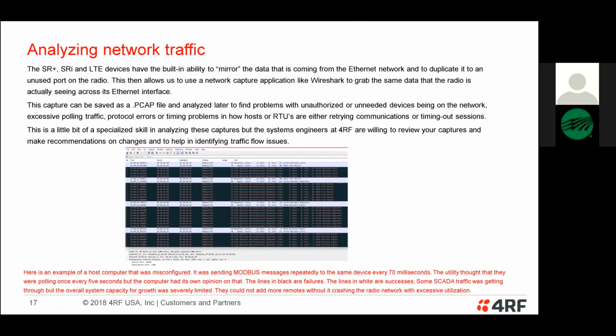And yeah, I agree with them. It shouldn't be a problem. But until we did a packet capture and looked at what was really happening, we weren't able to find out that there were so many reattempts by the host to get data that it was basically killing the entire network. And they were using a Modbus system because this is actually a water utility. While it was working with only a few remotes on the master, it would not allow them to grow the system. They had about 5 remotes on this master, but they wanted to bring it up to about 30 remotes. And when they started adding additional devices, it started taking down the first ones that were there. So packet capture allowed us to look at that.